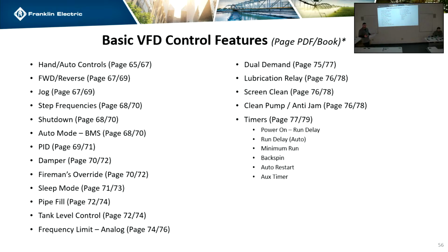It's pretty self-explanatory. It's going to ask you what type of unit you want to measure, what is the max range of the sensor that you're using, and what do you want to maintain. It'll ask you if it's inches of water column or PSI. Yep. So for HVAC, you'll turn it on. You'll go to units. You'll say inches of water column if you want, or bar. And let's say 15 inches of water column is the max range of the sensor. You put 15 in. You want to maintain, like 2 or 3 or whatever it is. You put that in there, and it's already automatically calibrated.